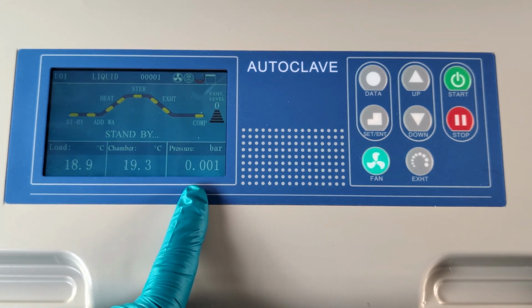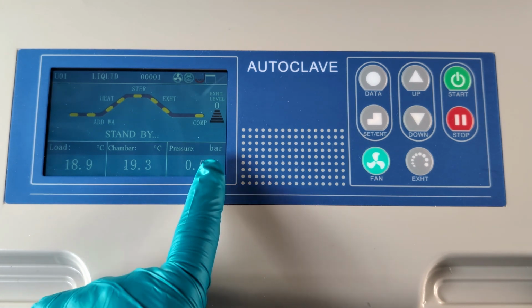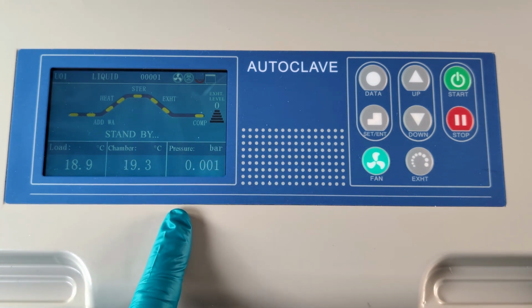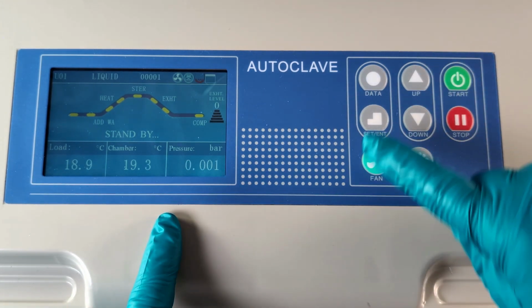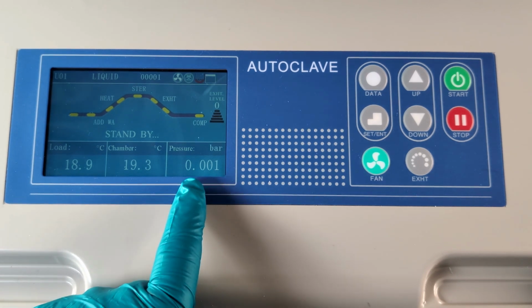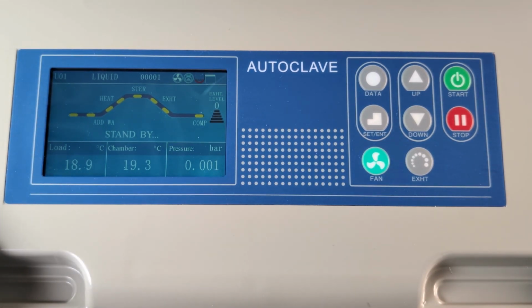Finally, on the right, you have the pressure gauge, which is set in bar, but you can also have it in pounds per square inch or in kilopascals. Again, you can change that easily using the controls here. You'll note that the pressure is around 0 bar or thereabouts. Now, this does not mean that you have a vacuum in the chamber, far from it. It means that you've got atmospheric pressure.